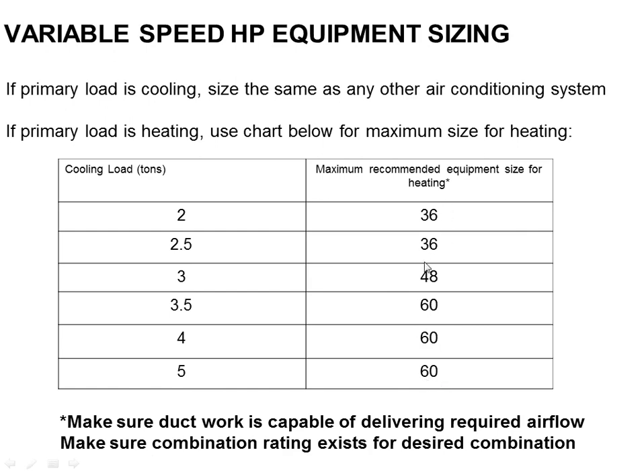So you can see just based on this chart why we don't stock a 2-ton heat pump, because it would apply to a system that was only like a 1 or 1.5-ton cooling load, which is a pretty rare house these days. So this is kind of the sizing chart, and you'll see the big giant note on the bottom that basically says pay attention to the ductwork airflow. There's no point in giving someone a 4-ton heat pump on their 3-ton ductwork system if they can't move that air. So you got to make sure you can actually upsize it in a retrofit scenario.